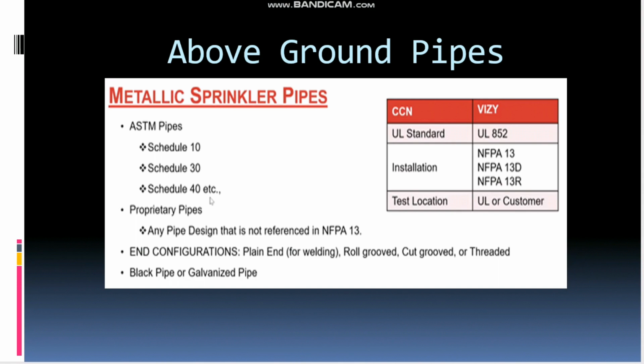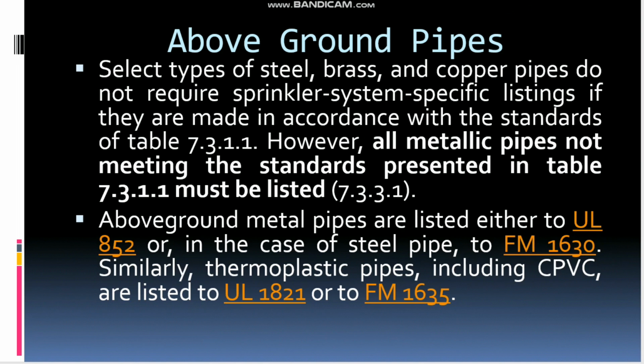And normally for firefighting, as I mentioned, we use ASTM schedule 40 pipes, and they can be threaded, welded, or a grooved arrangement, and the pipe can be black steel or galvanized pipe. Next, coming to the above ground pipe: as you know, mostly we use the standard pipe ASTM A53. We can also use ASTM A106, but ASTM A106 is a bit expensive compared with ASTM A53. And as I mentioned for the underground pipe, the same condition applies here also.